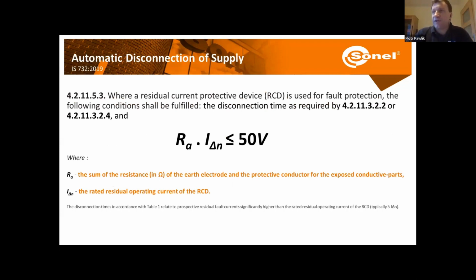Okay, so now in case we have networks secured with the RCDs, how do we check the disconnection time? Well, here we need to measure the resistance, which is the sum of the earth resistance, so the resistance of the earth electrode, and the resistance of the protective conductors. So everything that goes from the actual ground through the wall in our building up to our socket, this is the resistance, and we multiply it by the value of the rated residual current of our RCD. And this value should be lower than the long-term permissible voltage, so as the IS732 describes, 50 volts.